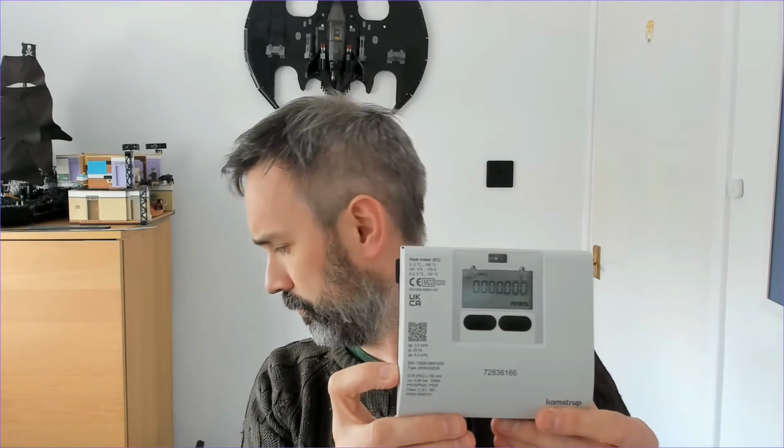So it's got basically a flow rate and the delta T, or the dT, between what's going out and what's coming back. Now on the unit there's a little meter reading here, and that will basically show you how much heat has moved at any given time. But this particular unit, which is a Kamstrup Multical, is it Multical? Yeah, Multical 403. This offers something called an MBus output.